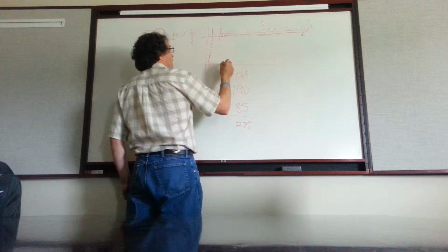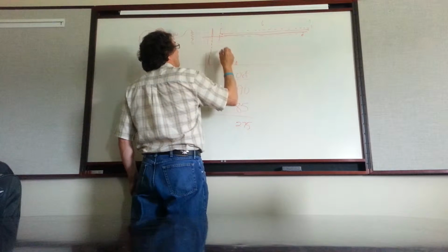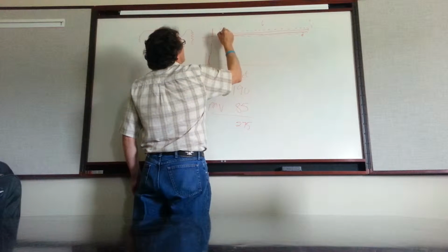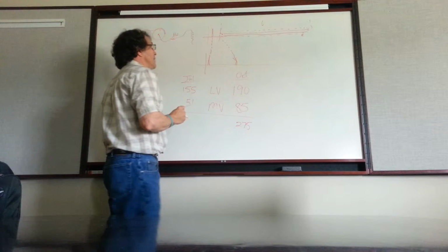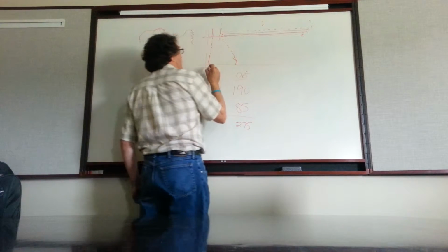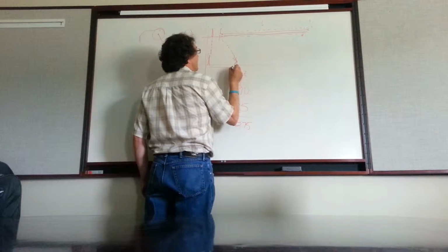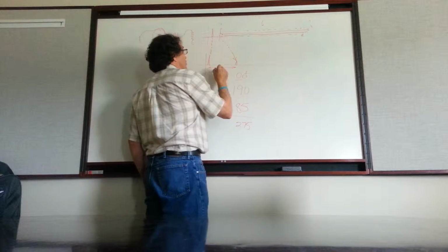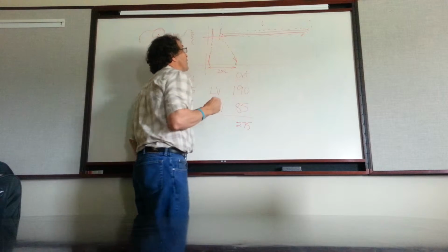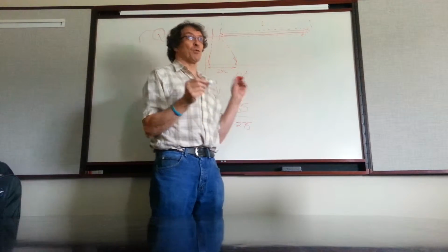And then the next one that you see is this guy. And it's attenuated because it's gone all the way down the cable and come back. And this distance here, in time, is 2 times L. Right. Because it's gone all the way down and come back again. So it's always 2L.